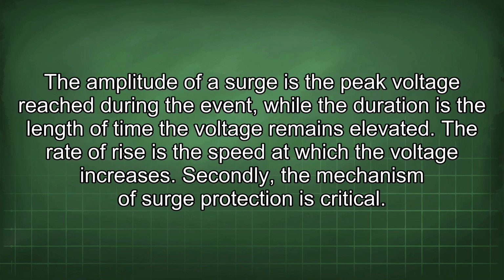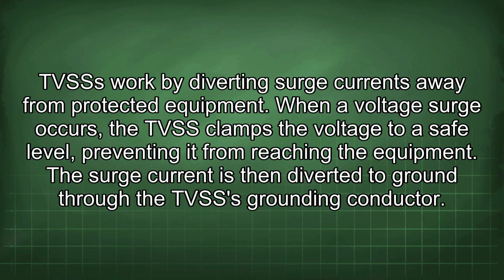The amplitude of a surge is the peak voltage reached during the event, while the duration is the length of time the voltage remains elevated. The rate of rise is the speed at which the voltage increases. Secondly, the mechanism of surge protection is critical. TVSSs work by diverting surge currents away from protected equipment. When a voltage surge occurs, the TVSS clamps the voltage to a safe level, preventing it from reaching the equipment. The surge current is then diverted to ground through the TVSS's grounding conductor.